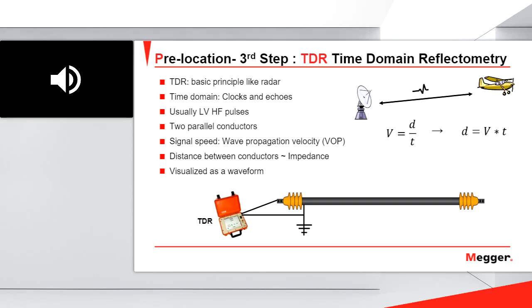In the case of the TDR for cables, what the TDR will do is send a low voltage, high frequency pulse. We could say that this low voltage pulse will travel through the cable with one leg in the conductor and the other leg in the concentric. Okay, and that pulse will go back to the TDR when it detects a change of impedance.